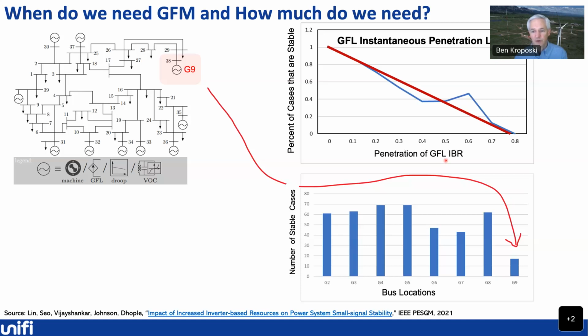And there's a tipping point where your systems become more and more unstable. It is also heavily dependent on where you actually place your inverters, and the further that they're out on the system or the weaker the grid that they're interconnected to, you're going to have more stability challenges. So these, answering the question of when do we need grid forming and how much do we need, it's very dependent on the system characteristics. This is a test system, but you could do this kind of characterization with any realistic system. It's also highly dependent on the types of disturbances and also the nominal voltage and frequency ranges that you want to keep your system into.